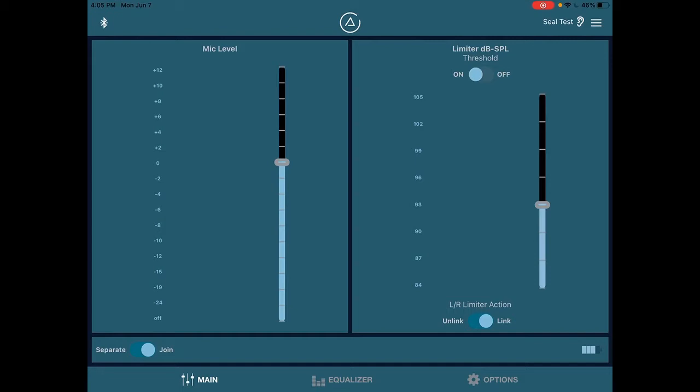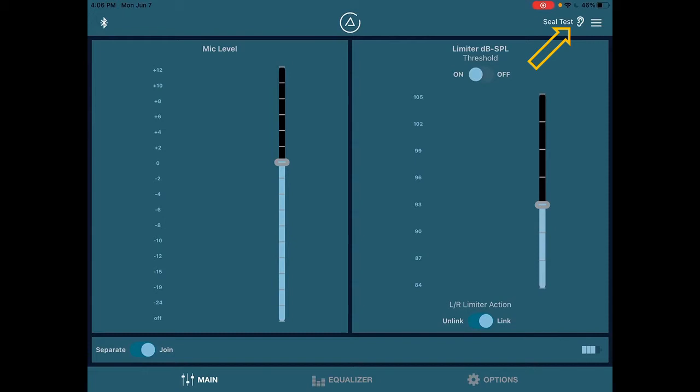So a couple of things on this main page. First things first, you have put the ear pieces in and maybe you want to make sure that you have a perfect seal. At the upper right hand side, there is a seal test. I highly recommend doing that. It will take you to a test that will play you tones and you'll be listening for them to see if you have a good isolating seal. If you fail the test, you might need to have different ear tips or maybe your insertion wasn't done well. So that's a really great tool to use. Also at the bottom right hand side, you can see a battery. That is the battery status of the belt pack of the 3DME.